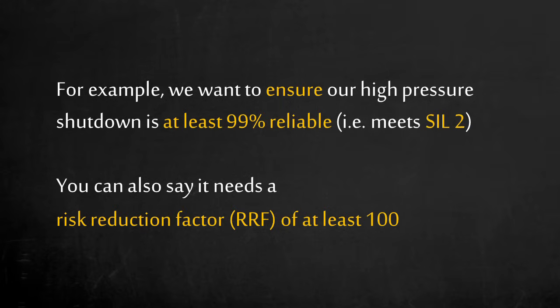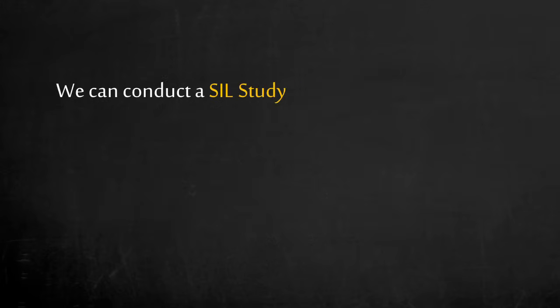We claim that our high-pressure shutdown is at least 99% reliable, or in other words, that it has a risk reduction factor of at least 100. As a safety critical function, we want to ensure it can meet SIL 2. How can we systematically make design and operation decisions to meet the safety integrity level we need? We can conduct a SIL study, which is also called a safety integrity level verification in the IEC standards.